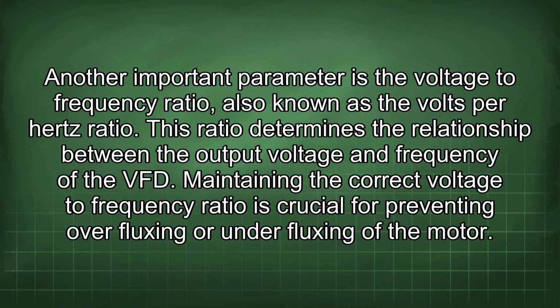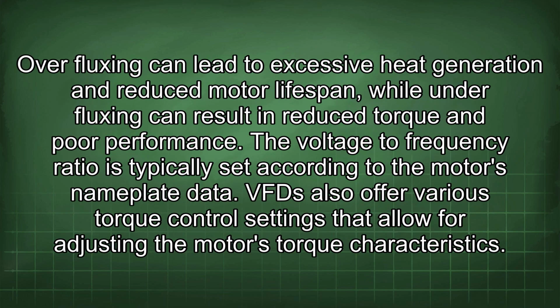Another important parameter is the voltage to frequency ratio, also known as the volts per hertz ratio. This ratio determines the relationship between the output voltage and frequency of the VFD. Maintaining the correct voltage to frequency ratio is crucial for preventing overfluxing or underfluxing of the motor. Overfluxing can lead to excessive heat generation and reduce motor lifespan, while underfluxing can result in reduced torque and poor performance. The voltage to frequency ratio is typically set according to the motor's nameplate data.